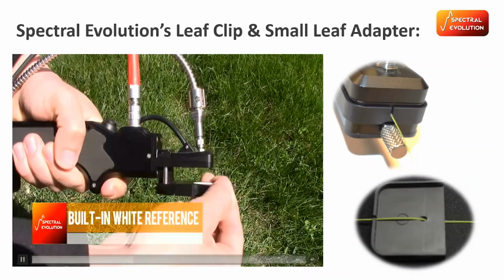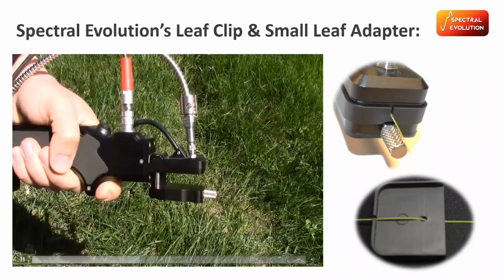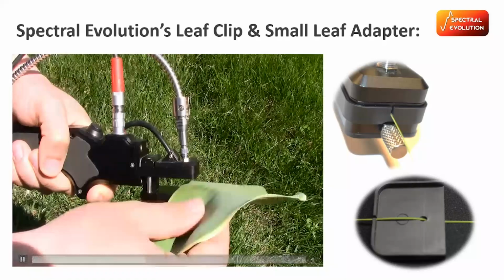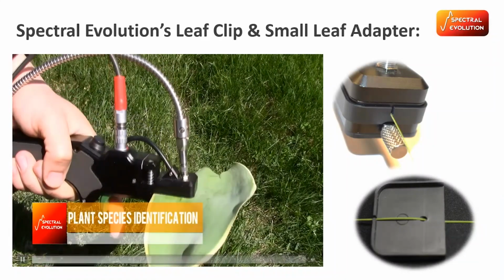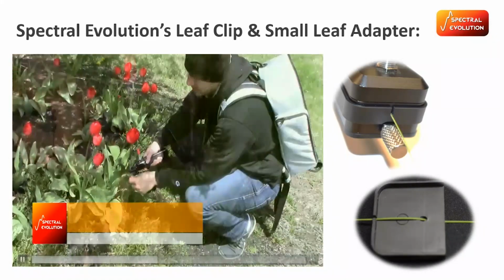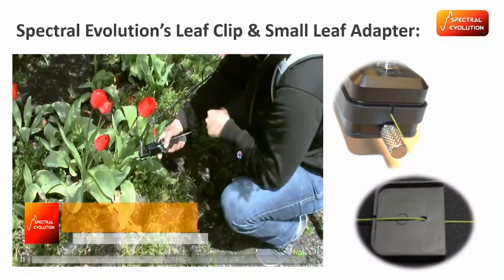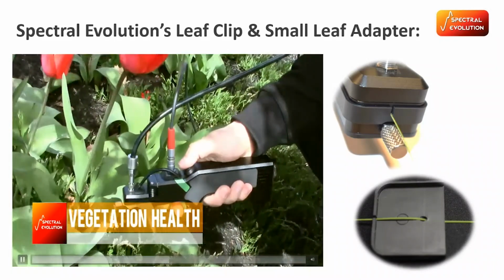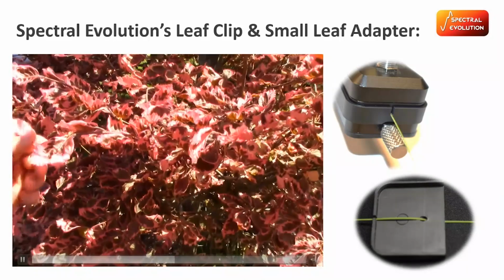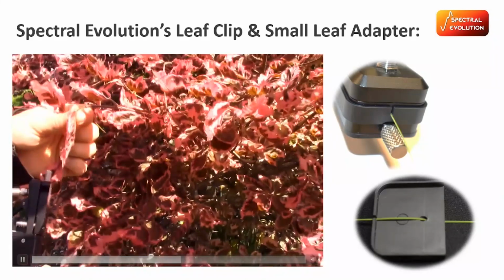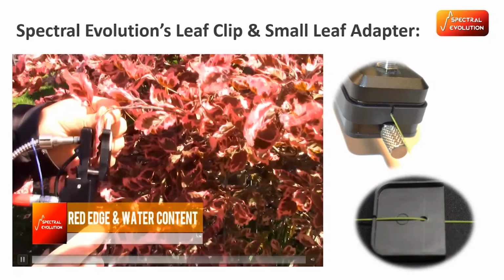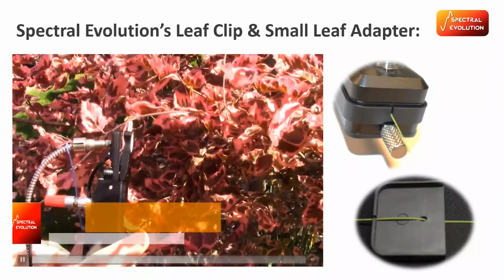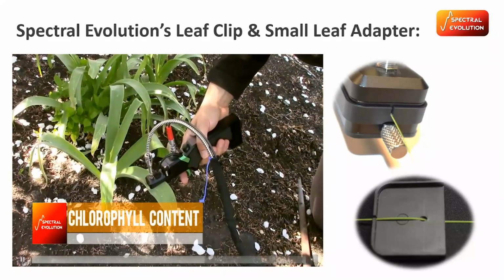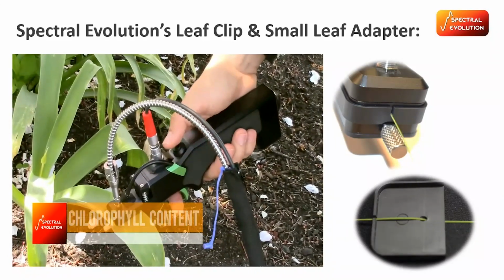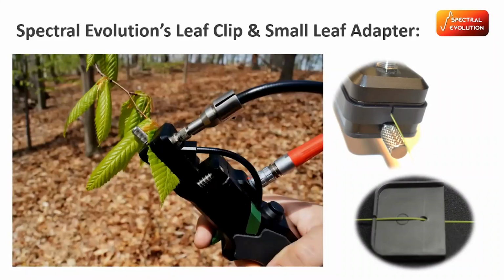And all of this works with our Darwin software, which operates the instrument and allows you to take scans and catalog them. You can create spectral libraries for comparison in the future. You could build up the library in the lab using the surface probe, then go out into the field and compare to that with a one-to-one geometry, and use EasyID to match between leaf analyses. So you can do things like chlorophyll content and things like that.